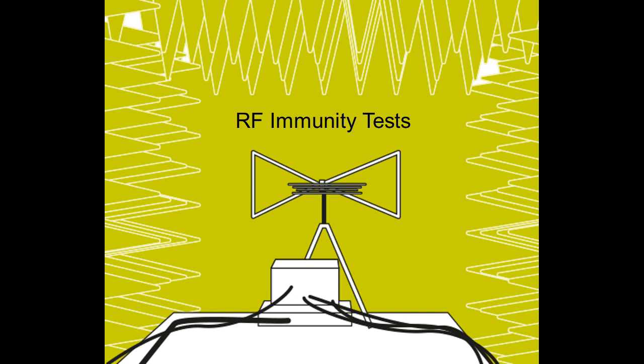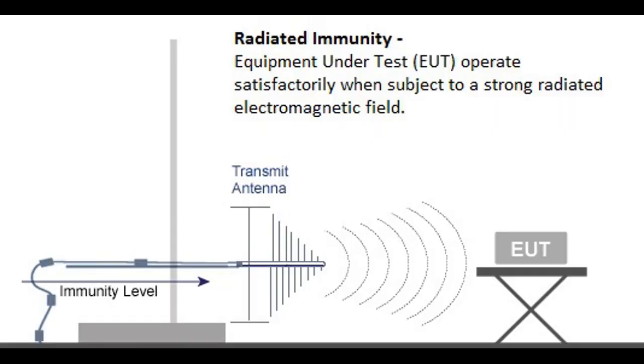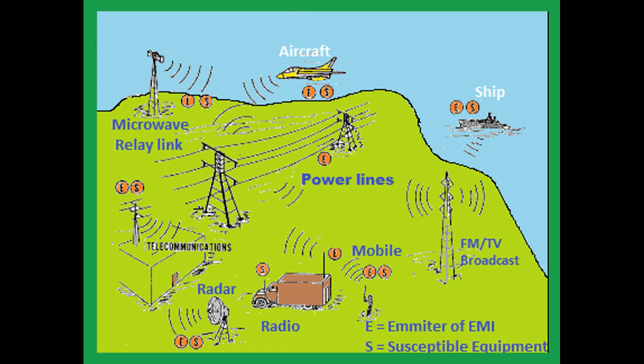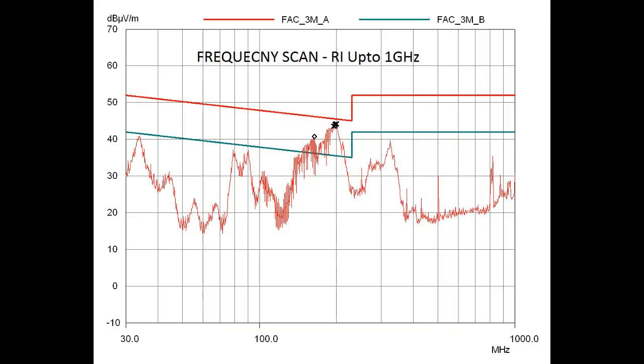Hello audience. Today we will discuss radiated RF immunity. Immunity testing requires that the equipment under test operate satisfactorily when subject to a strong radiated electromagnetic field, such as might be created by cell phones and other intentional radiators, and RF noise that might be caused, inadvertently or otherwise, by industrial processes. This requires a frequency scan at a certain fixed level of field strength.